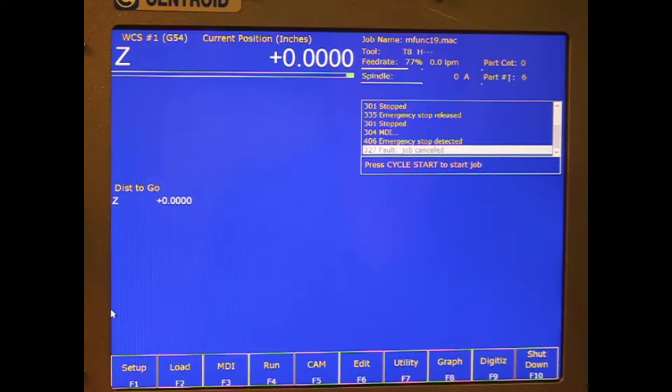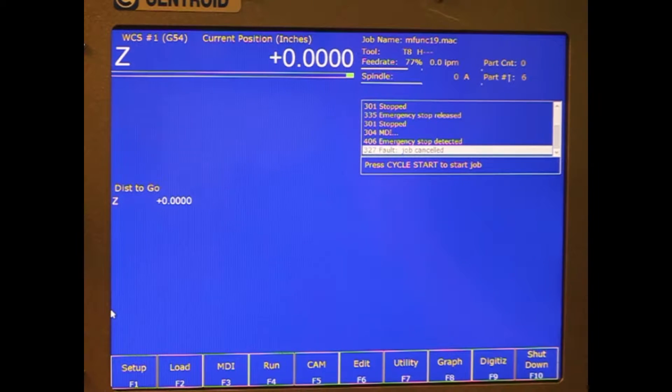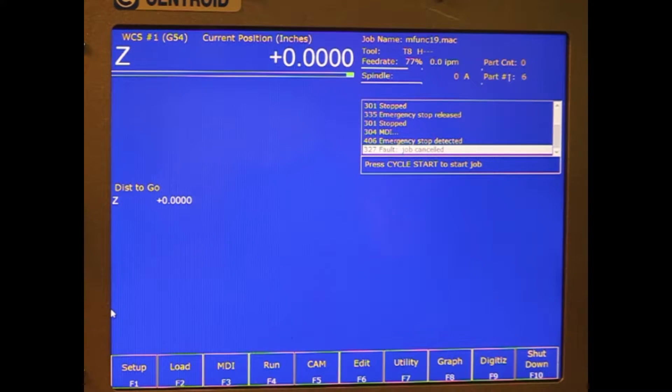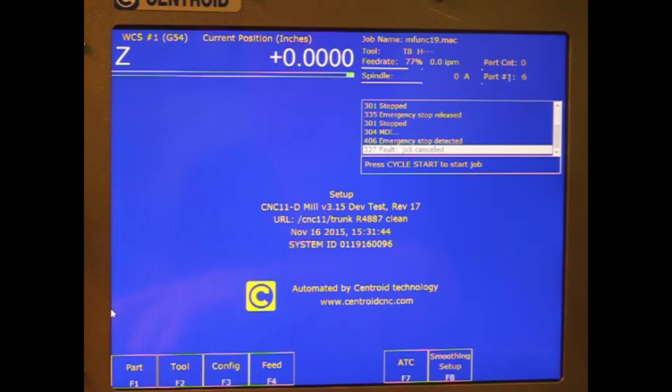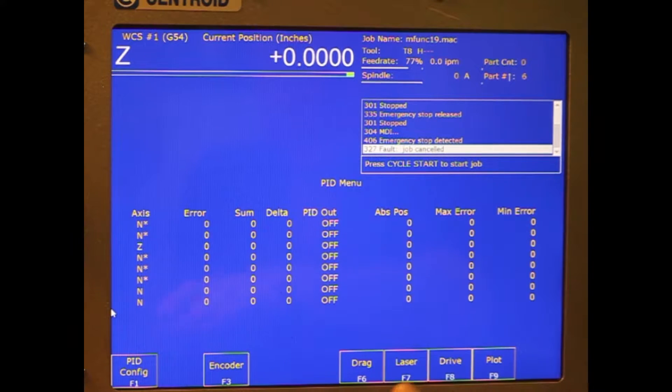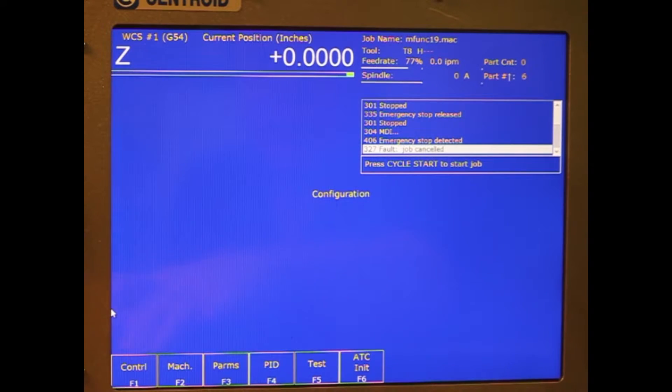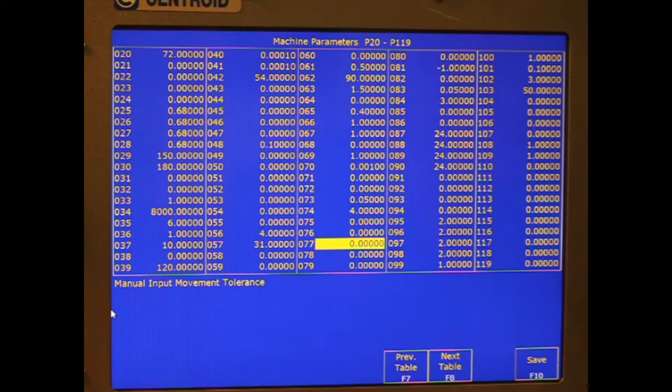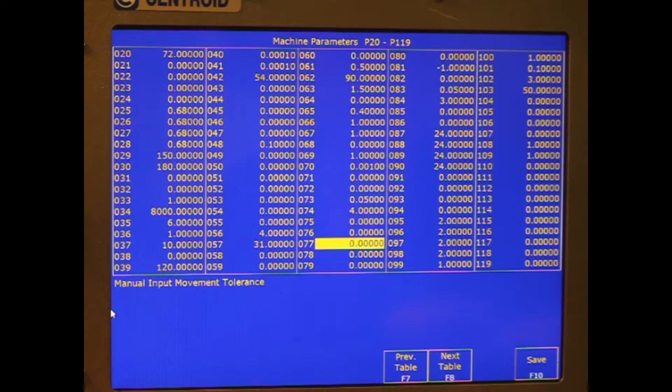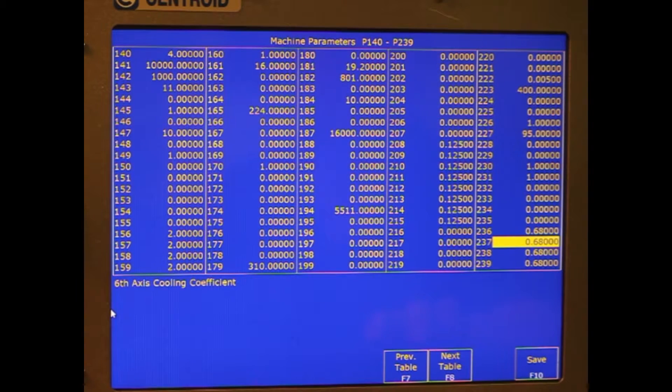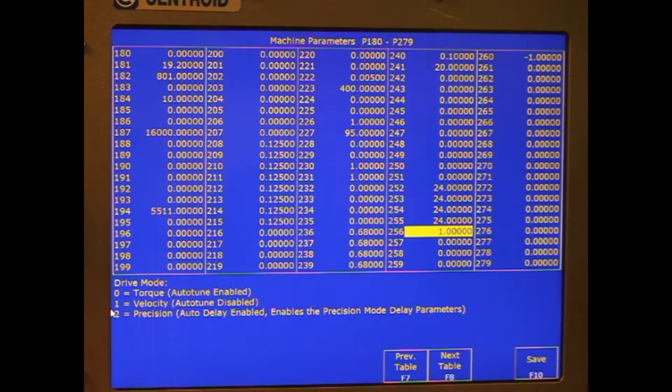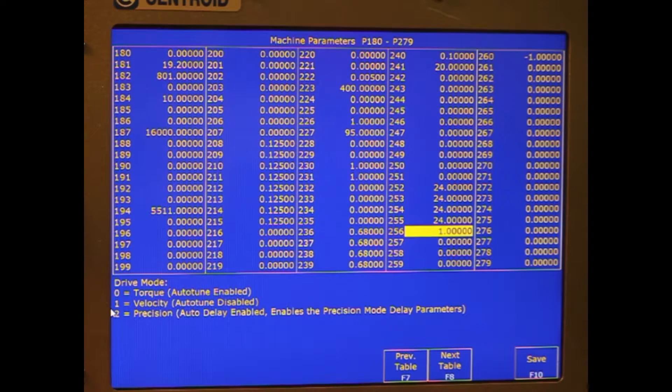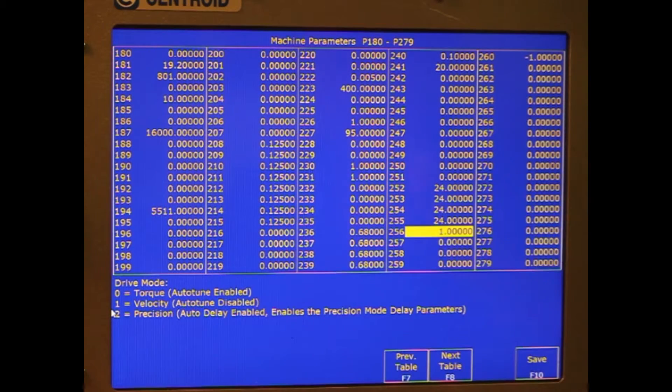One of the first things that we need to do is there's a few parameters that we need to set up. Let's tell it for velocity mode. We're going to go into the parameters, and parameter 256 needs to be set to a 1, which is set up for velocity mode.